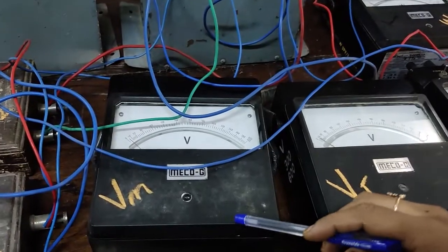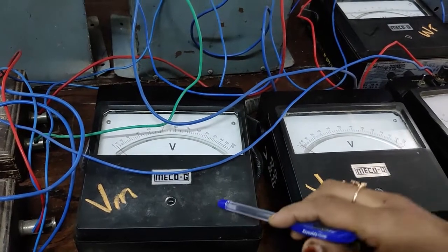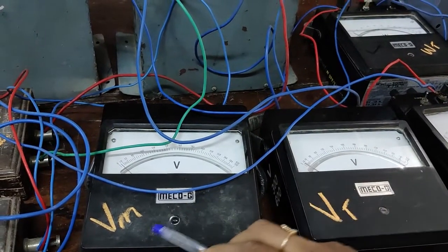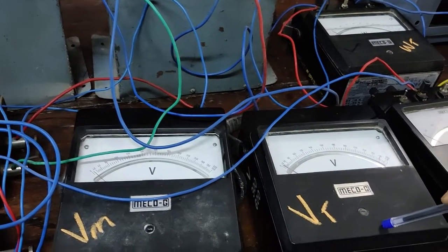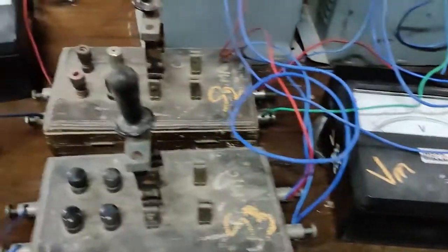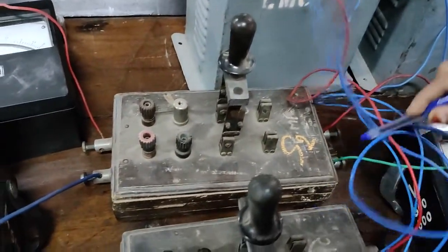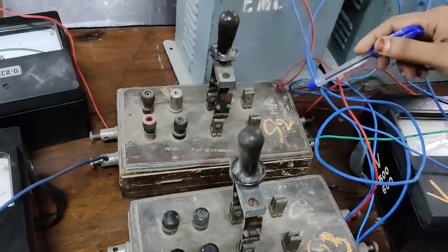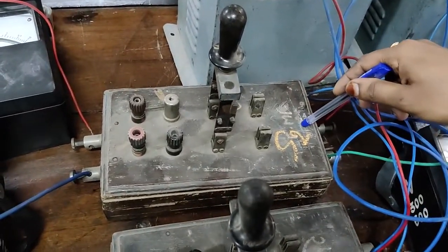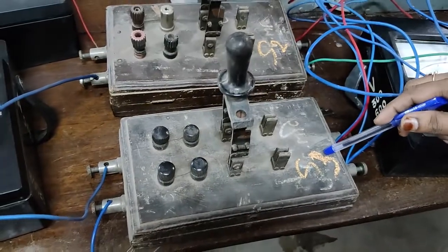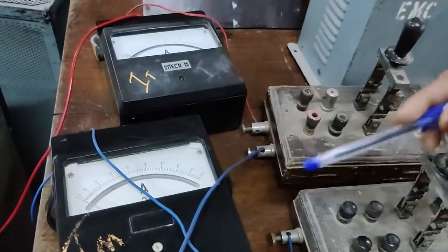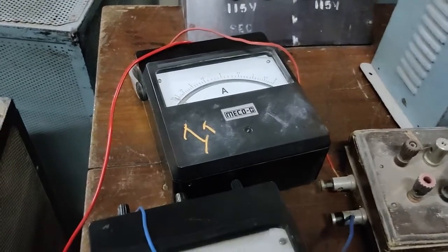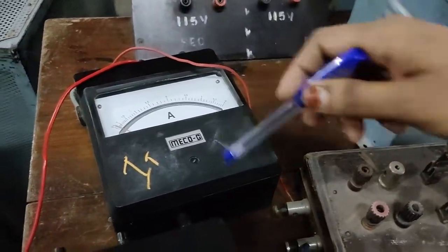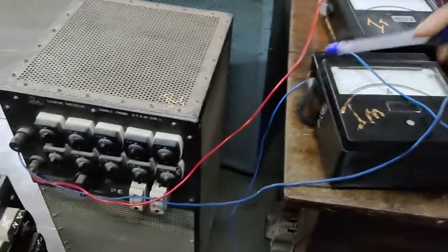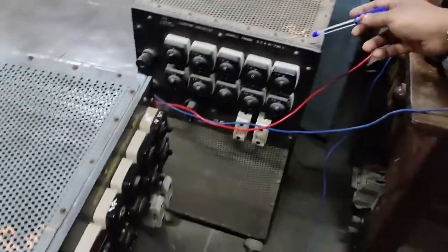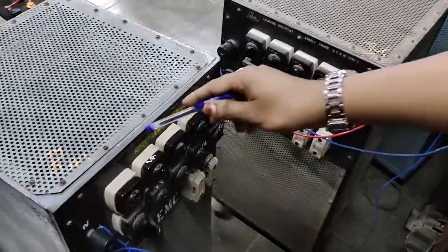And for measuring the voltage in the secondary side or the loading side, for the main transformer it is VM, and for the teaser transformer we have VT voltmeter here. And the loads are connected through switches, and for the teaser transformer it is S2, and for the main transformer it is S3. And as per the circuit diagram we have two ammeters in the load side, IT and IM. And we have two loading rheostats, RT for the teaser side and RM for the main side.